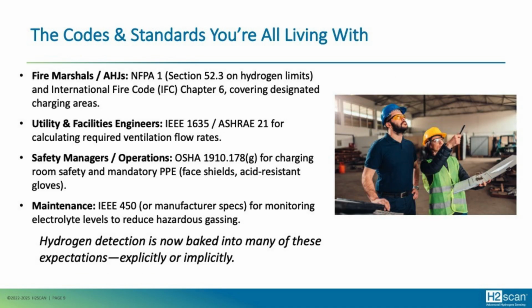So there are lots of different standards documents as well as code documents that exist. The International Fire Code is the most popular model code for fire codes in each state. And then, of course, you have OSHA and other governing bodies when it comes to safety of people. So for engineers who are designing systems, you have international standards such as the IEC and also IEEE and ASHRAE documentation for ventilation methods and how much ventilation should be passed through an area to mitigate the hydrogen based on the number of batteries and battery types that you have.